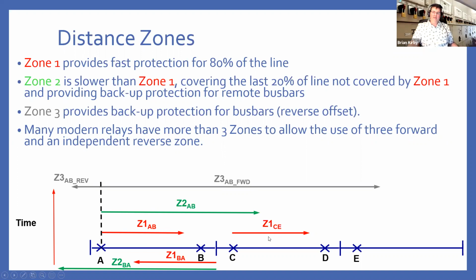However, if for some reason this relay didn't see the fault, say it's very close to the inlet here, so that end doesn't see it because it's only 20%, and this one, it's such a small measured voltage that you can't accurately detect it, then your zone 2 from the previous zone gives you an overreaching protection. So this is our, if you remember, our overlap of protection that we're talking about at all times. And then just to be absolutely sure, we tend to have a third zone, which is slower again, but much longer reach.